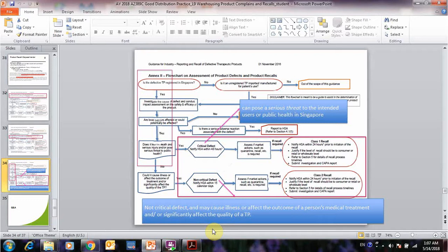The recall message, which is your Dear Purchaser letter, needs to indicate whether the recall should be carried out at a retail level or wholesaler level or customer level, and also the class of recall needs to be very clear. Alright, if the recalled product is exported to another country, and if you are a manufacturer or the supplier of this product, the overseas counterparts need to be informed, and of course the overseas regulatory authorities must be informed on the recall as well.